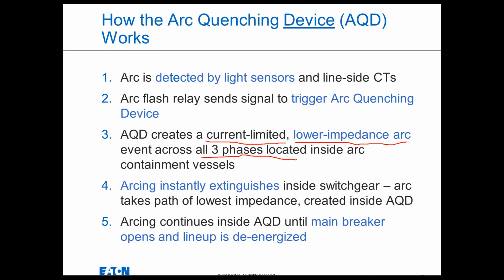So that causes the arcing to instantly extinguish inside the switchgear, and all that arcing current, all that energy, flows into the arc quenching device and is contained inside it. There it continues to arc inside the arc quenching device until the upstream breaker opens up and de-energizes the lineup.